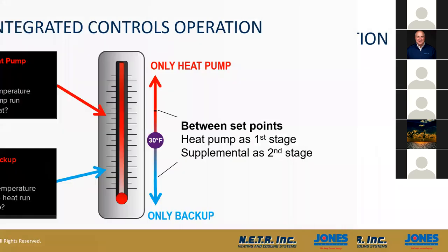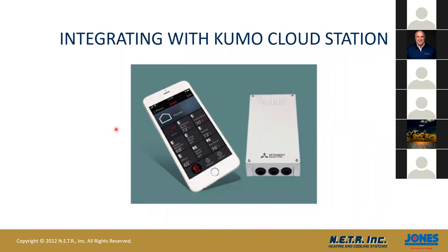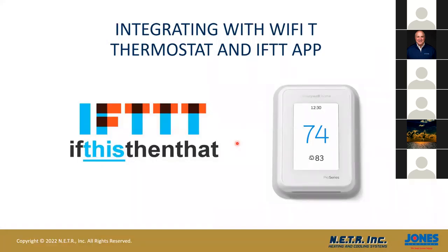The way we integrate it, there's a couple different ways. Mitsubishi Electric has a Kumo Cloud station that we would put near your boiler. And these channels that are right here, we would integrate with your boiler and with Kumo Cloud and tell the system at a certain temperature, hey, turn my boiler off, put my air source heat pumps on for efficiency. And you can also use it with a system that's called IFTTT. That's an app. IFTTT stands for if this, then that. What it does is below a certain temperature, it will tell the system to turn the system off, put my boiler on, or put my air source heat pumps off. Basically just shifting between the temperature with a weather app that is on there.